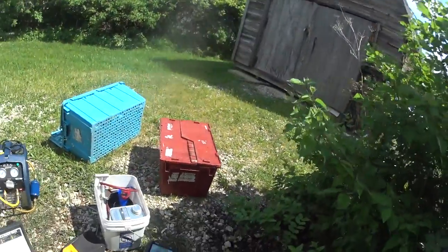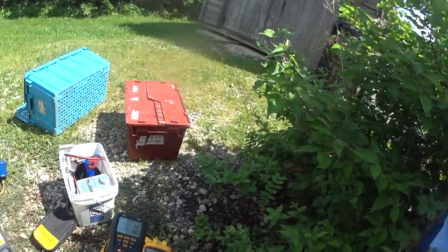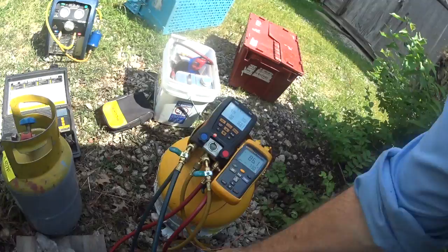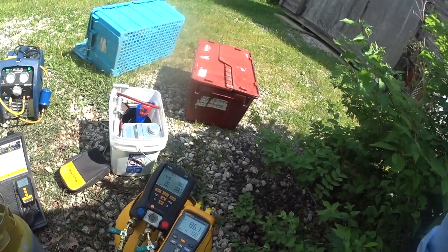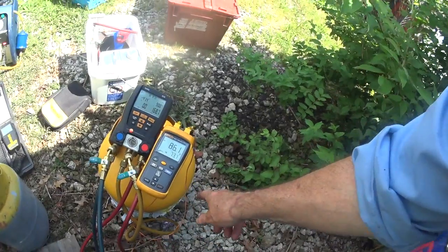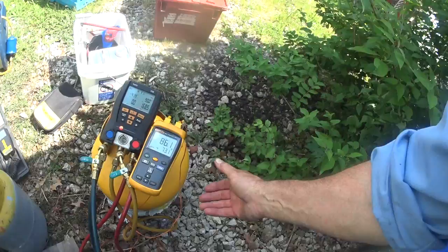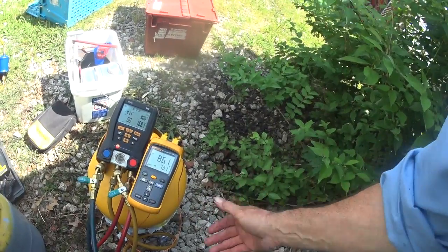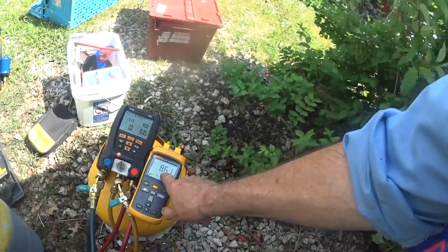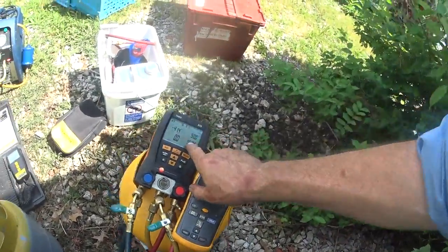This is a quick little something that's kind of interesting to do. I put T1 to the bottom of the tank — I taped it on where the liquid is — and I've got 86 degrees. This is the R-22 refrigerant that I just reclaimed, and I want to check the integrity of it to see what kind of condition it's in over all the years. I've got 86 degrees on the liquid refrigerant.